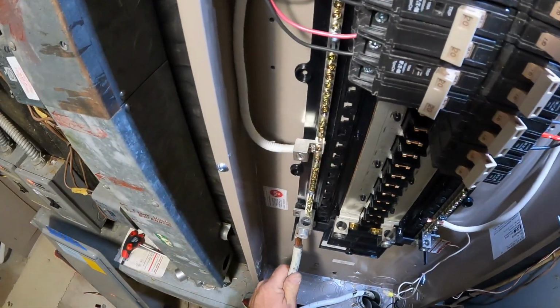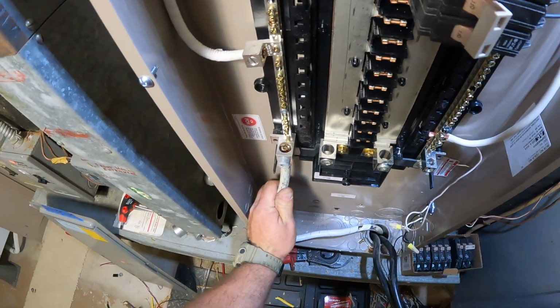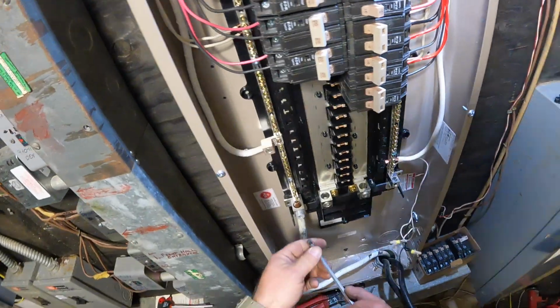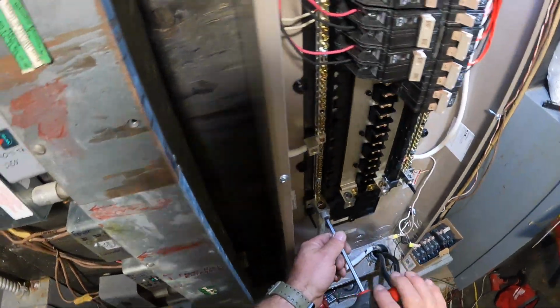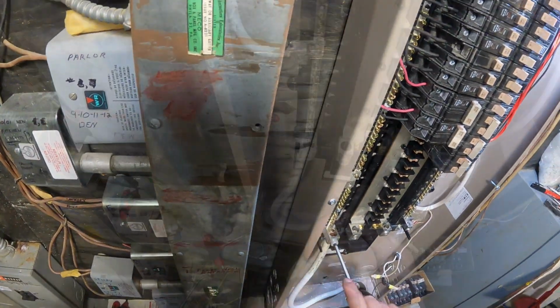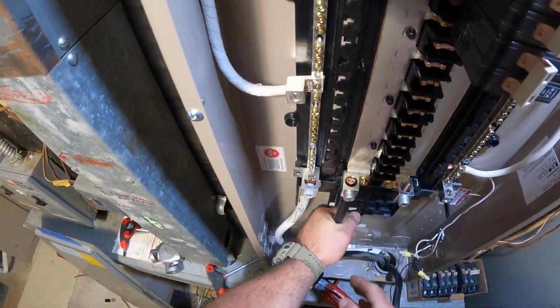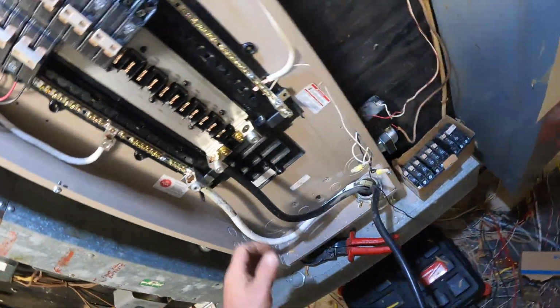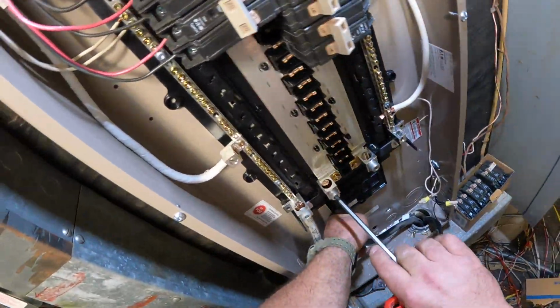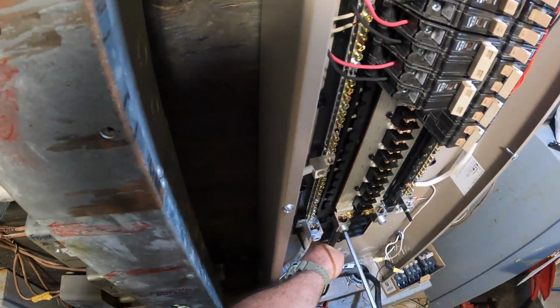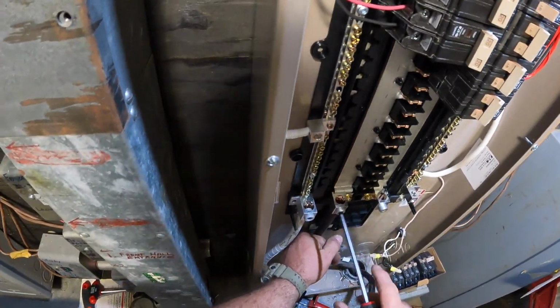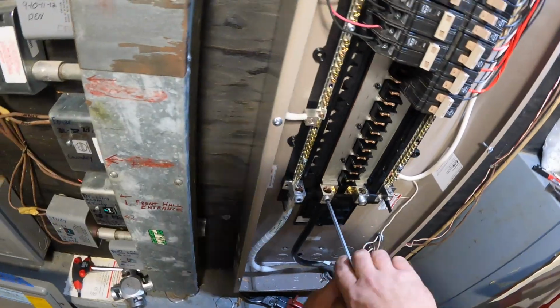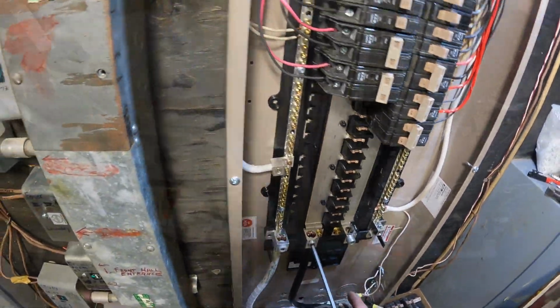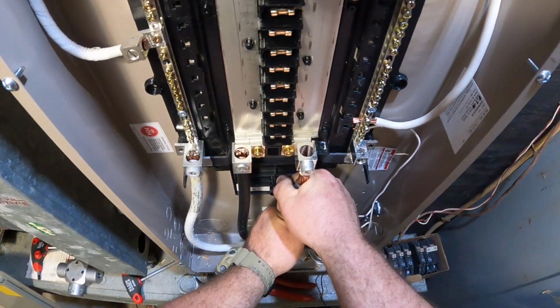I'm a real fan of identifying my conductors. Even though that conductor is already white, I'm putting new tape around it to re-identify it so there's no doubt it's a neutral. The code actually calls for that, and I cringe when I see other electricians just put one little piece of tape around there and call it identified. Some inspectors would be okay with that, but if I was an inspector, I'd want more identification - I want that conductor completely identified.